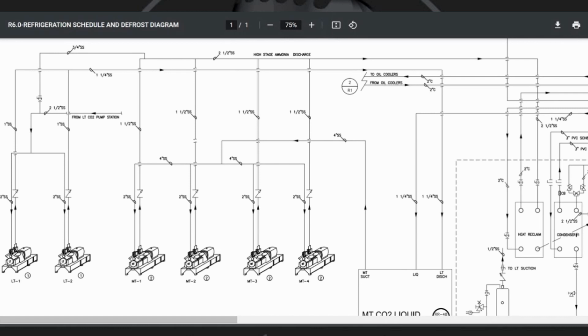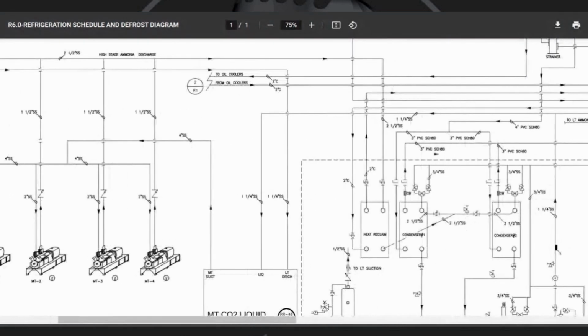Right here. And we're running a 2-inch water line on the other side of that plate heat exchanger. And we're trying to raise the water from about 80 degrees to 120, 130. Okay. There's about 75 GPM going in there. And depending on the load of the compressors and the load in the store, we get anywhere from 200,000 to 350,000 BTUs heat of rejection out of the heat reclaim plate heat exchanger.